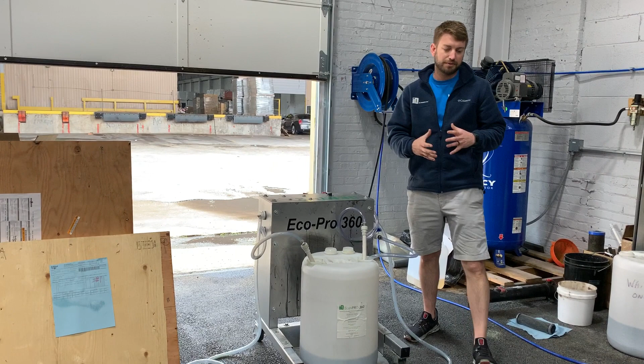But with the shutoff, obviously we're plumbed into the bottom here. If my supply side was on the top, obviously we're not going to fill up the top half of this heat exchanger, and we're only going to clean it partially. So with the shutoff, this is going to allow me to pump the chemical in and really fill up the heat exchanger before opening up that valve and returning it back through the filter and into the cart, and then we start our flushing. So with that, I'm going to show you how to do this.